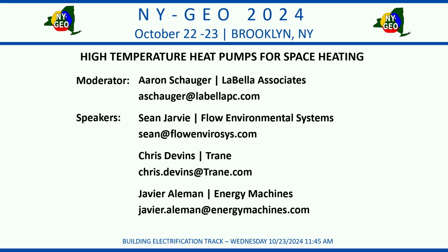Andrew Macaluso, Watts. This question's for Sean. When you're using transcritical systems, I know a lot of times they're targeted at very high delta T's, high lifts, because it's a requirement for transcritical. How are you able to achieve the low delta T's required for a space heating system, and does that have a negative impact on performance?